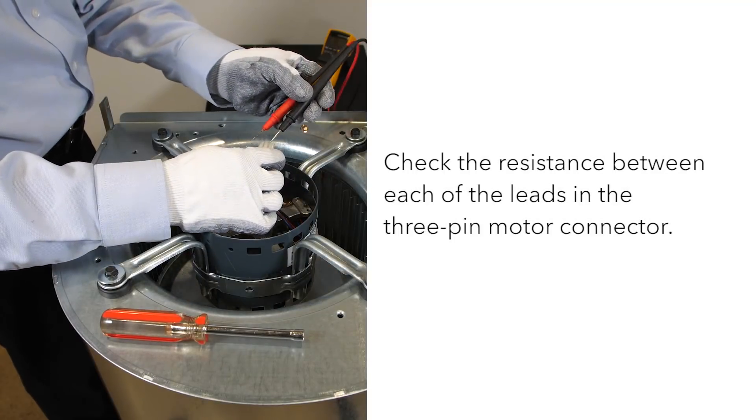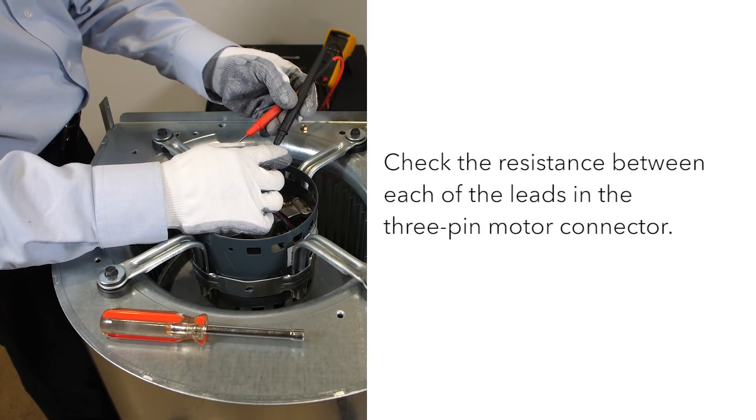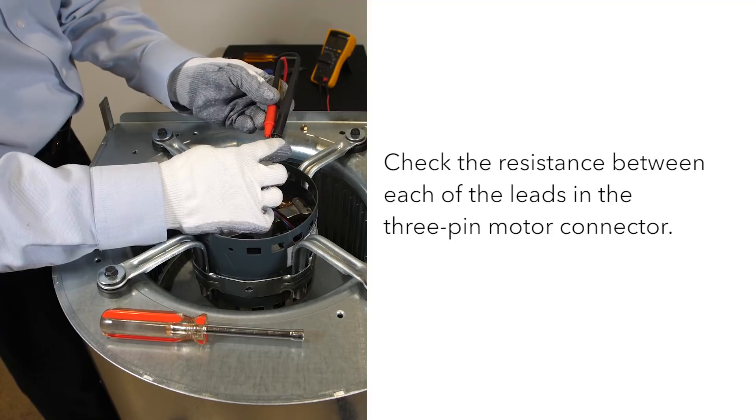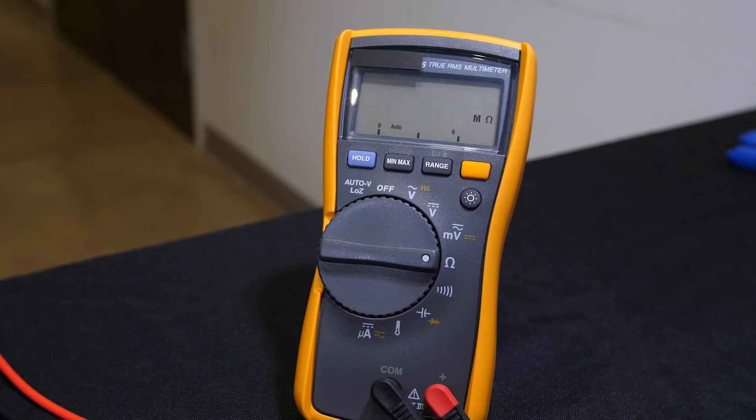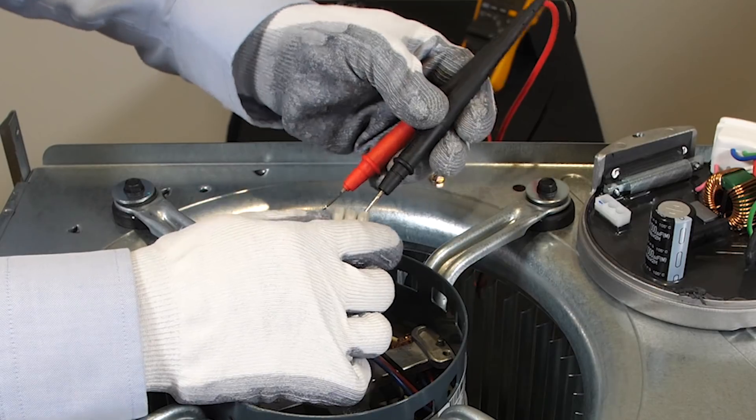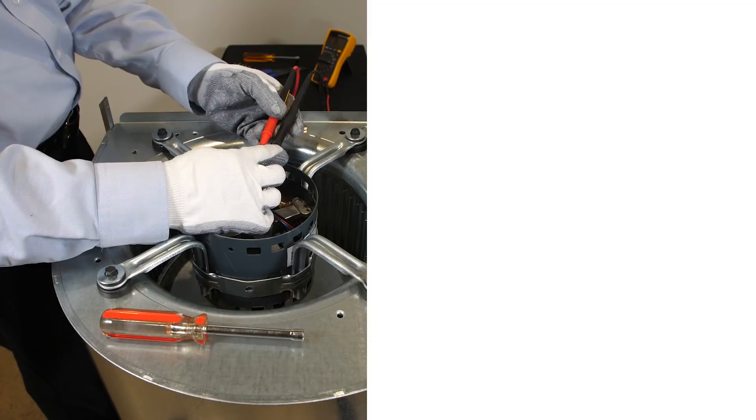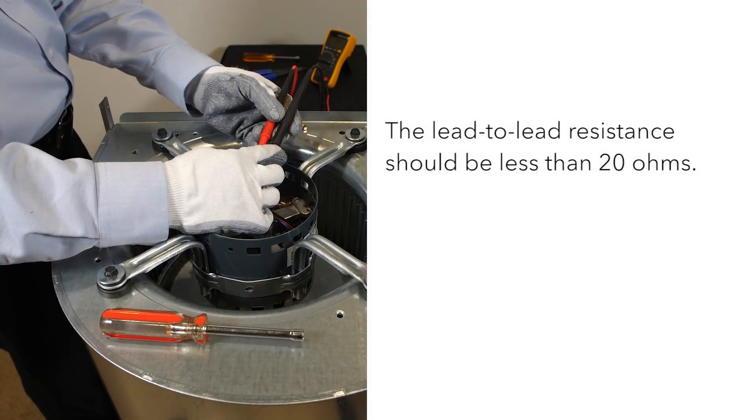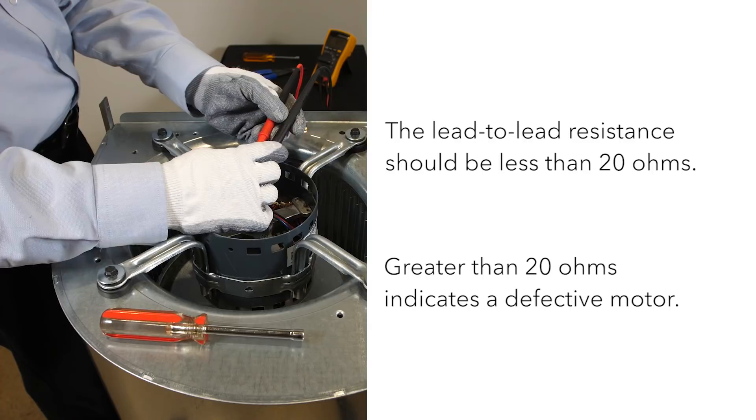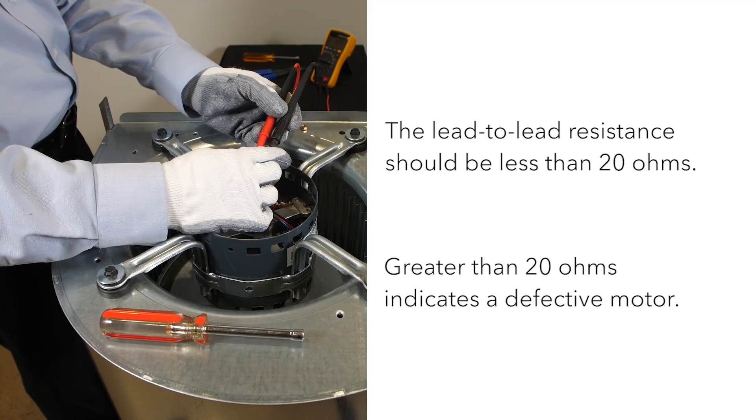Check the resistance between phase to phase by checking between each of the leads in the three pin motor connector. The lead-to-lead resistance across any two leads should be less than 20 ohms and each lead-to-lead resistance should be the same within plus or minus 10%. If this test fails and you have greater than 20 ohms, it means you have a defective motor and it needs to be replaced.